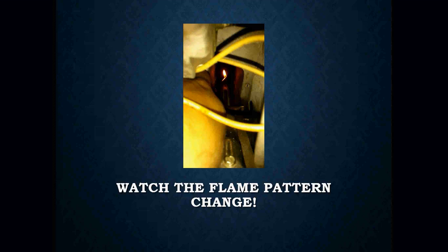Now, you can do that with a simple grill lighter, as you see here in the video. You don't necessarily have to turn the burners on to see whether or not a heat exchanger is cracked. However, there are cracks in a heat exchanger that may not necessarily show their ugly face when the heat exchanger is cold. So sometimes this test may not necessarily work. So my recommendation in a lot of cases is to do it both ways. Do it with just the blower on with a simple little grill lighter. Go across each one. Then do it with the burners on the furnace actually lit and watch the flame pattern to see whether or not the flames actually change.